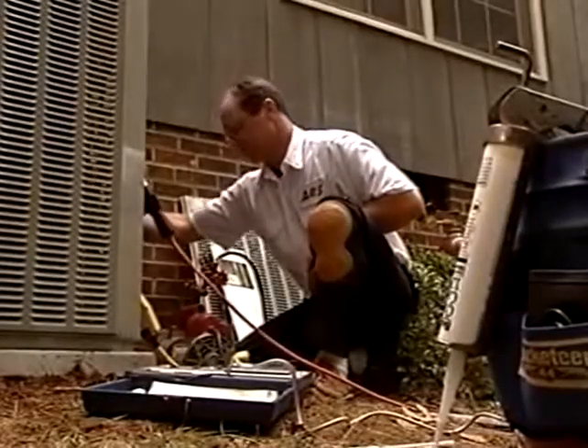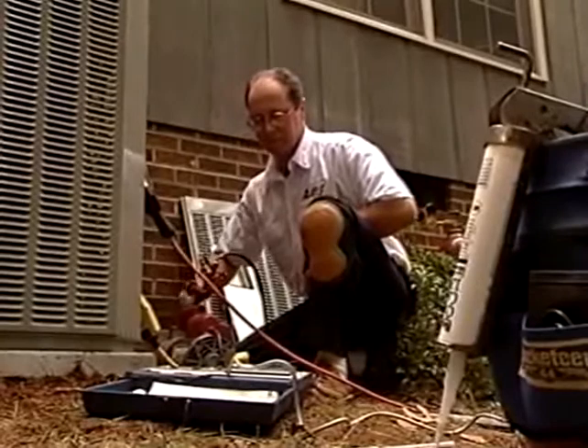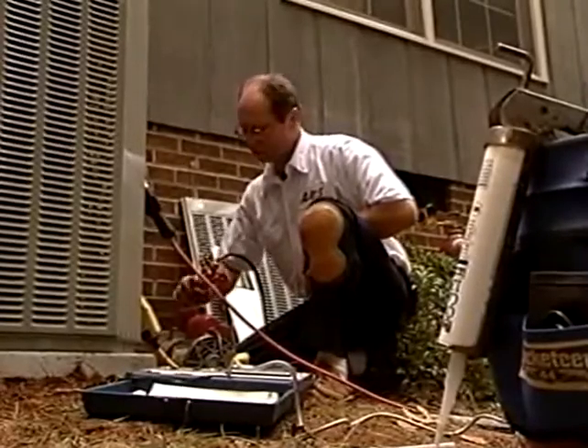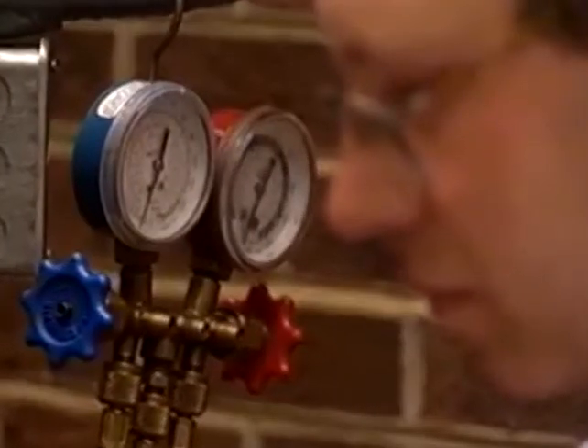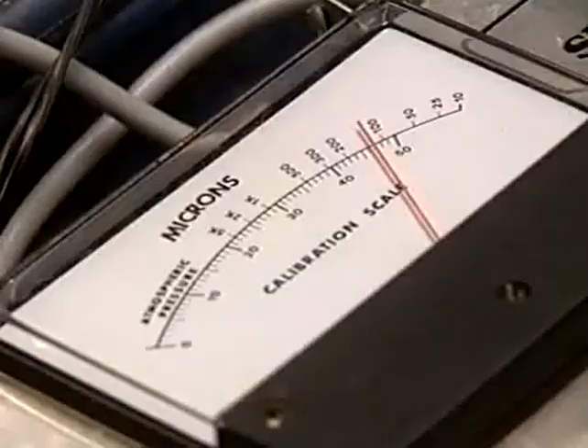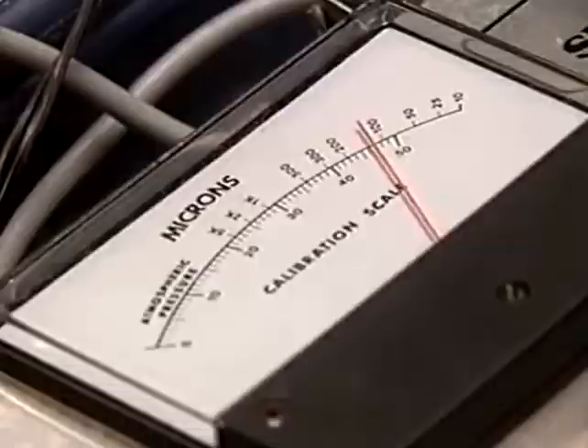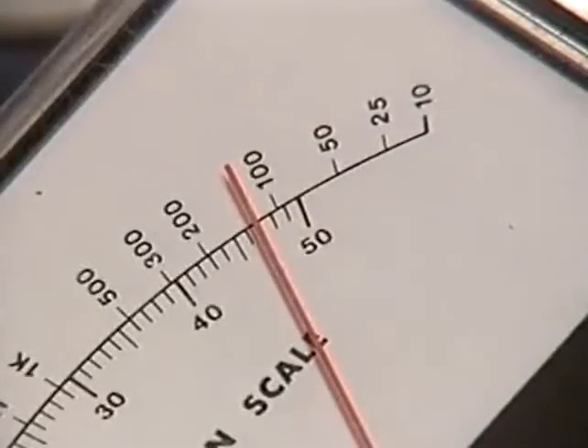Finally, once the refrigerant lines have been installed, you'll need to pressure test to check for leaks. This is done by pulling a vacuum on the line using a vacuum pump and a micron gauge. The problem that we have going on out in the field right now is that very few contractors own a micron gauge. And so they can't measure how well their vacuum pump is performing. All they know is that it is pulling refrigerant out of the system, but they don't know how well it pulled out. They think it pulled enough or well enough.